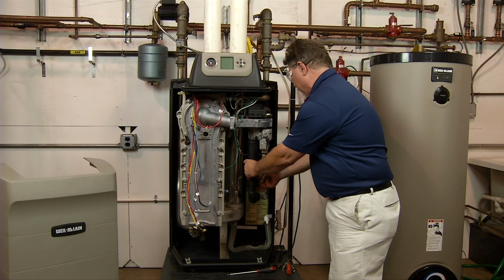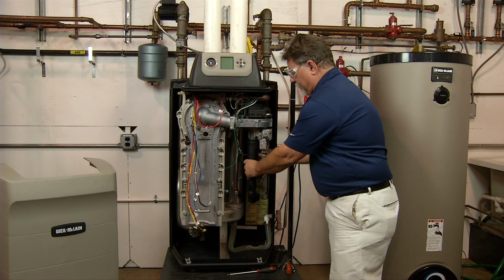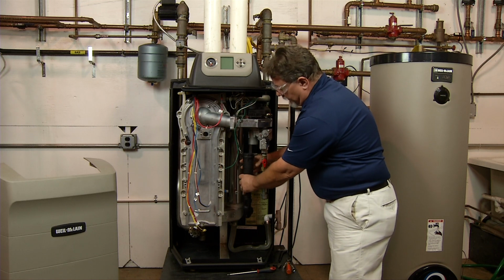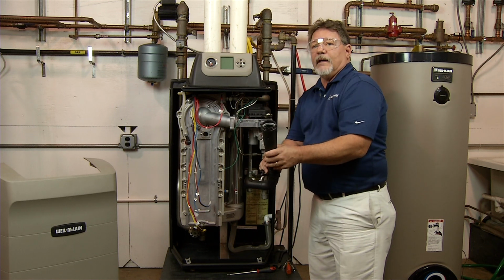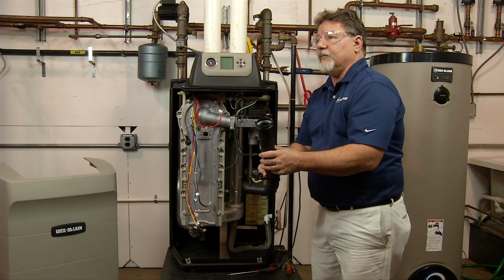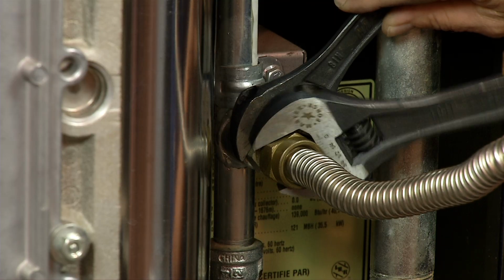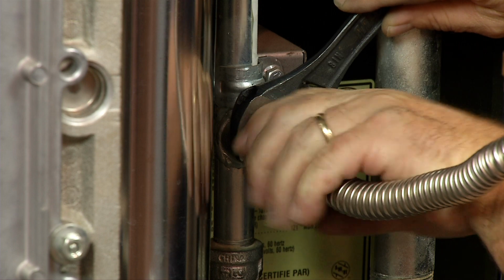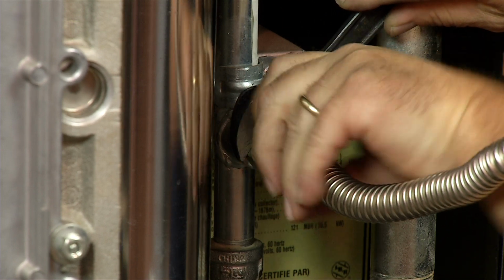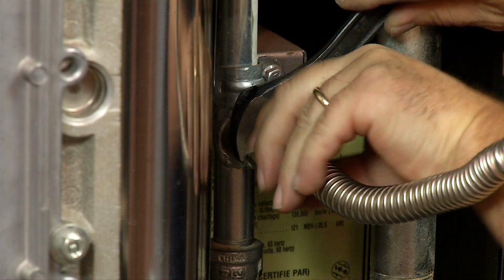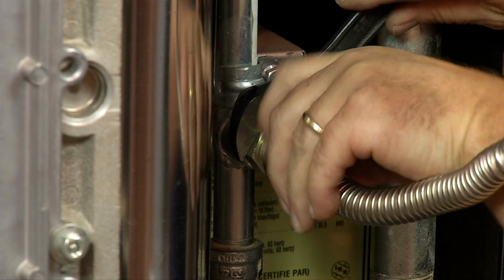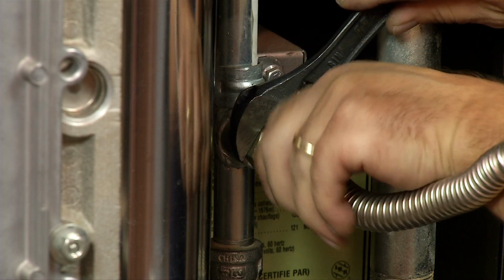So we're going to remove the clamp on the gas line and gently pull down on the air intake piping or the silencer, and we'll set that aside. We also need to remove the gas line using a couple of wrenches here, and this is a compression fitting. We simply want to loosen that up and remove it.